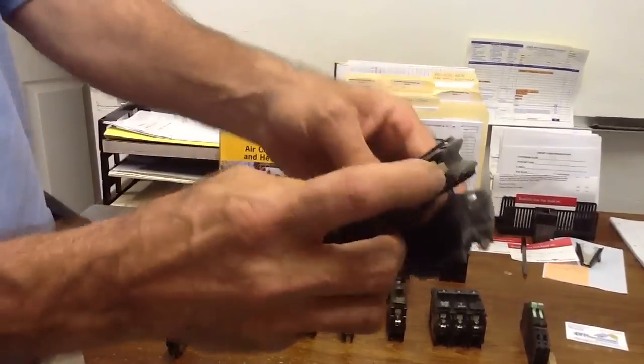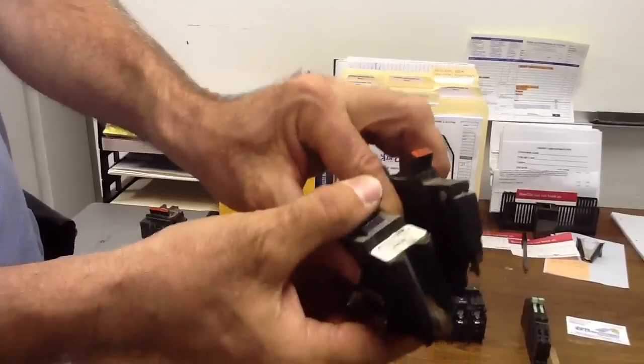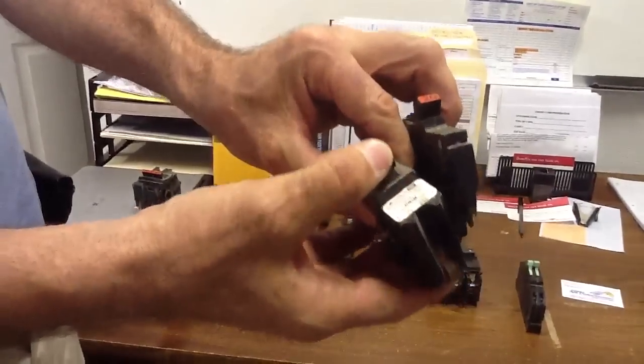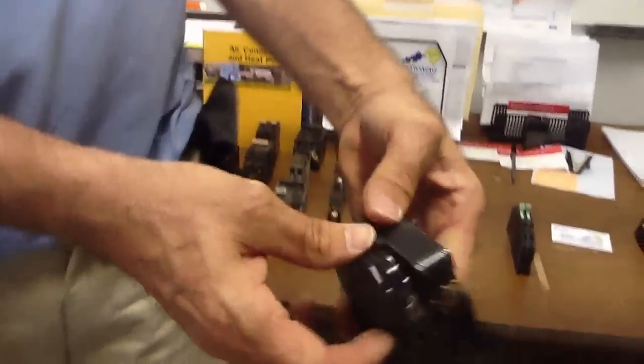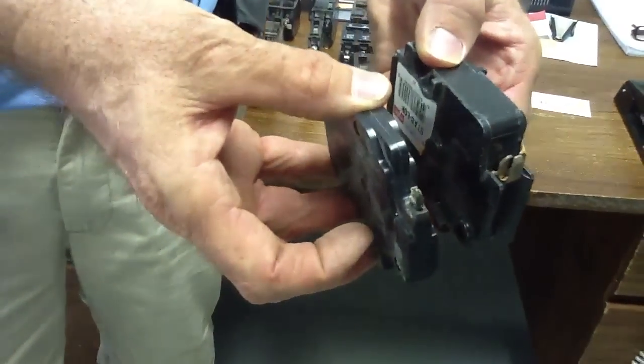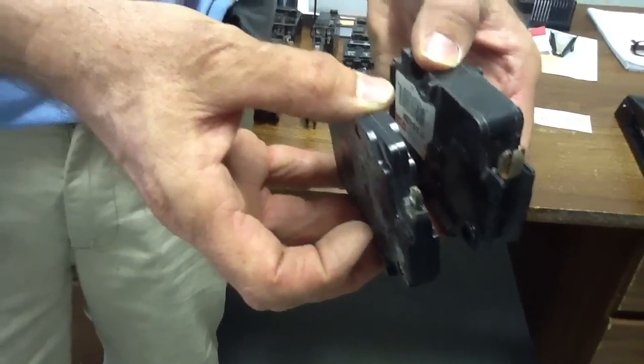Here is a fat single pole breaker, Federal Pacific, see the stab lock. This one actually sounds pretty good. I would use this one. Here's the difference, thin and fat. So that was another drawback with Federal Pacific, they have the thin and the fat.